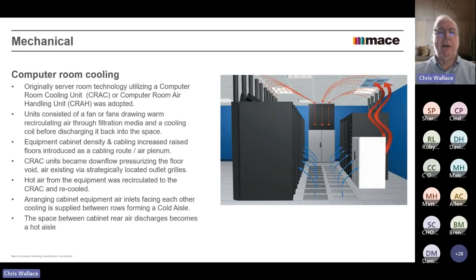How have we done it historically? Originally, you had the famous CRAC unit or CRAH unit, depending on what you want to call it. They were basically drawing the warm air back from the computers, circulating it through a downflow unit, and typically blowing it through a plenum raised floor, which was also used as a cabling route. You pressurized the floor, put the outlets where you needed the load, and then the hot air went back to the cabinet. A little while ago, some clever people realized that the equipment cabinets took cool air in at the front and blew the hot air out the back.